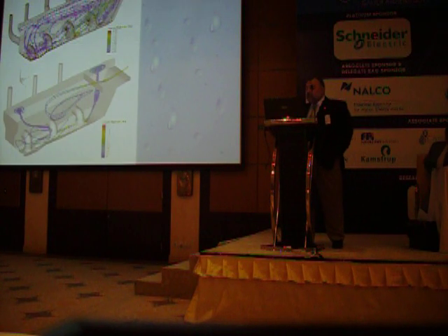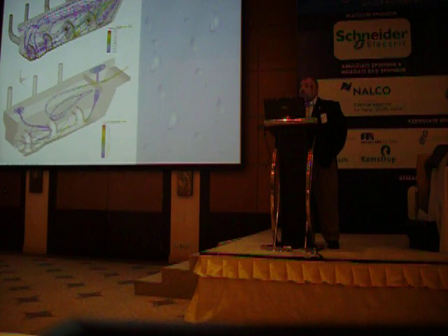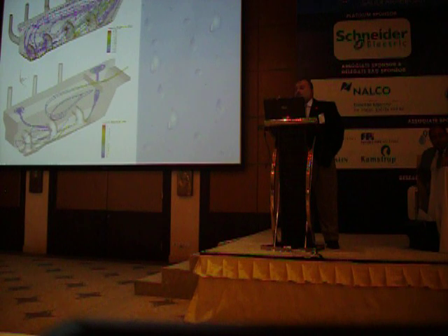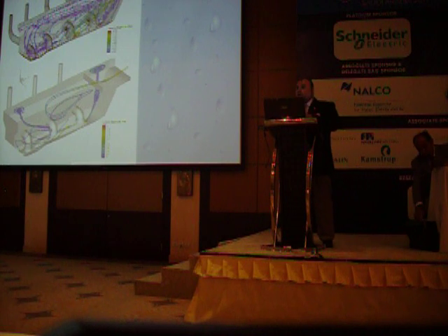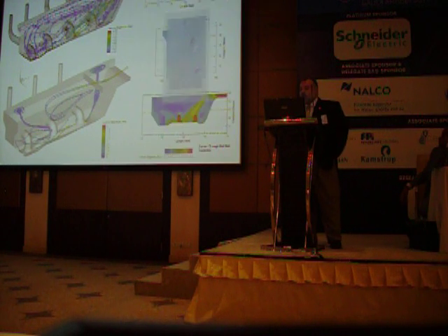Here also we can continue with one of the most common practical examples, the streamlines of the previous example regarding the pump pre-swirl rotation. You have vortices surrounding the pump, and the suction of the pump can entrain air. Also, how the pump shape will be fixed, and the bell mouth shape or the pump inlet, how it can affect the geometrical design of the pump well itself.